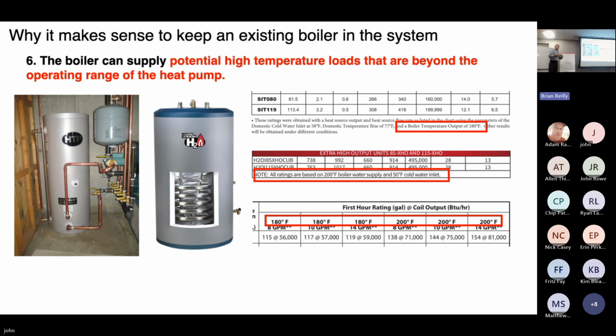So if we take an air to water heat pump, even if it could do 140-degree water, and we just connect it to a small and potentially scaled coil, anybody know what's going to happen? Speculate. The heat pump is going to short cycle. The heat pump is going to produce heat at a certain rate, but the coil can't accept heat at that rate. So the temperature between the heat pump and the coil just keeps going up, and it goes up quickly, and there's an internal temperature limit in the heat pump.